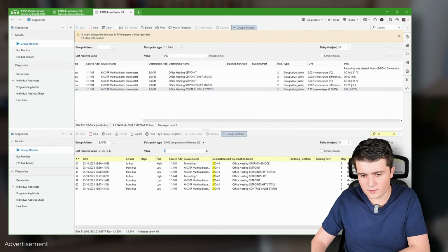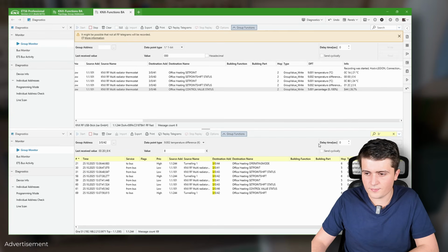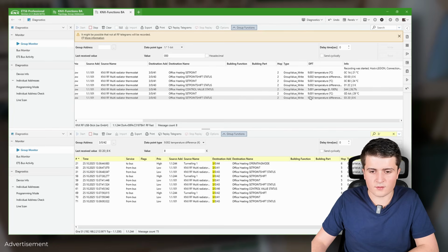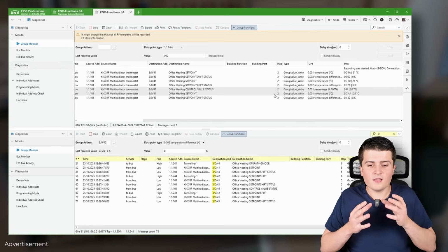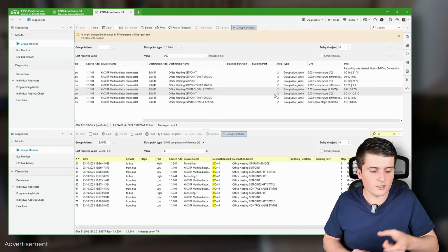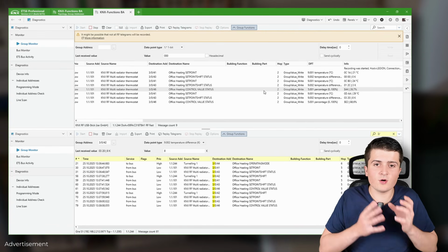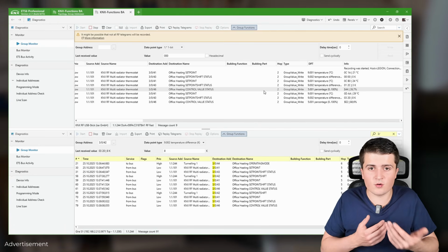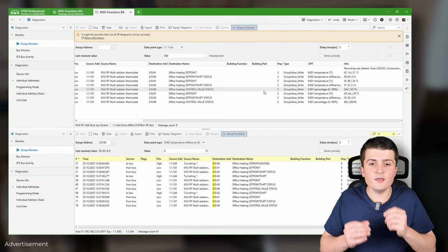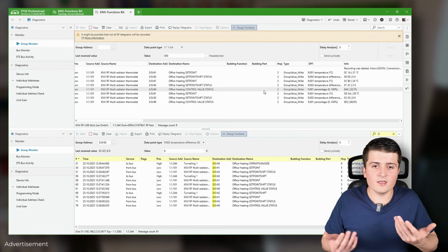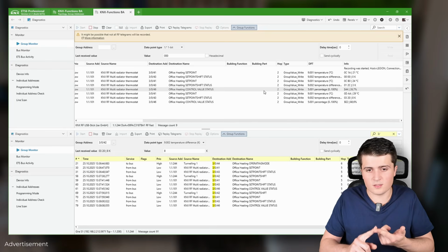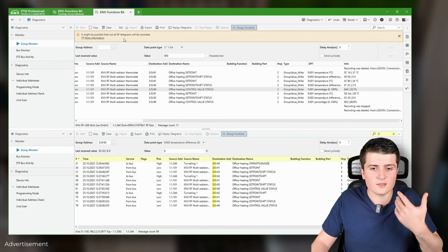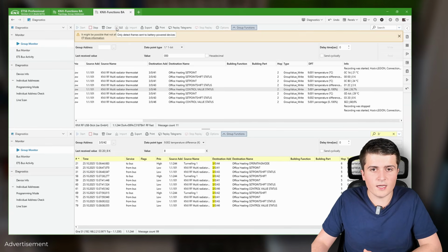I can even go further to 8 Kelvins, click on write, and then we can see here the response. So this is what you should remember: when you monitor KNX RF Multi with such a USB stick, you can only see one communication type or one mode, so fast or slow mode, at the same time. If you would want to see both, well, then you basically would need 2 USB sticks, one running fast communication, one running slow communication. Now, in order to see the slow communication, you have this button here on top, SLE.